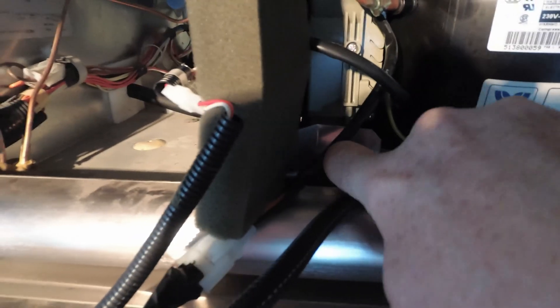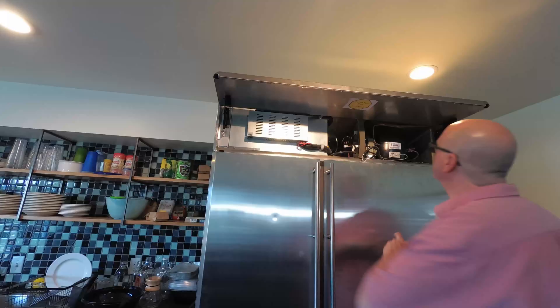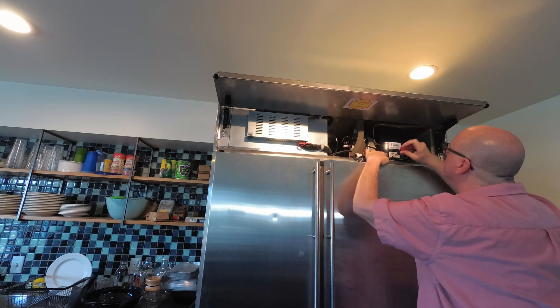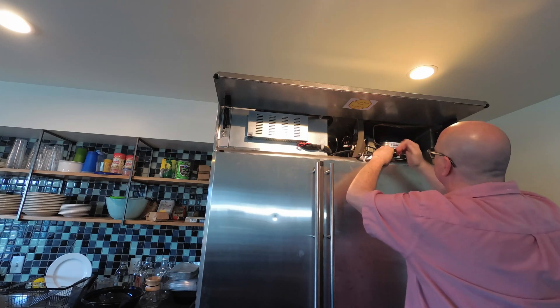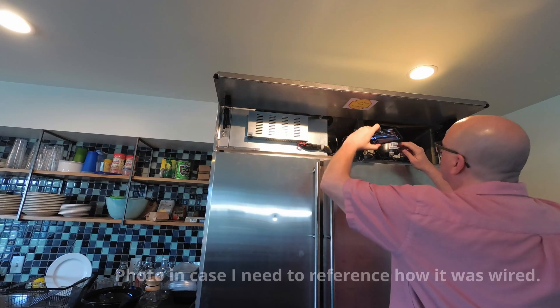That gray board in there is the inverter for the three-phase motor in the compressor. The black tub is the compressor, and that gray box is the inverter. Here I'm loosening this panel so I can move it to the side and get some clearance to pull that box out once I loosen it.